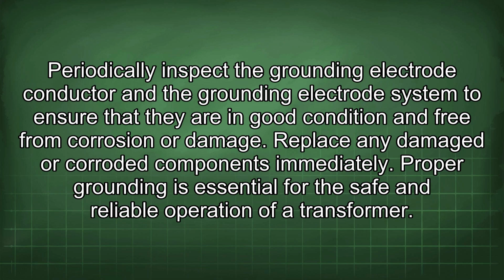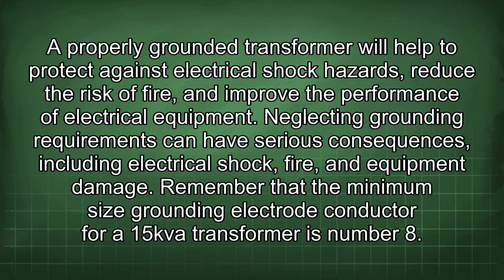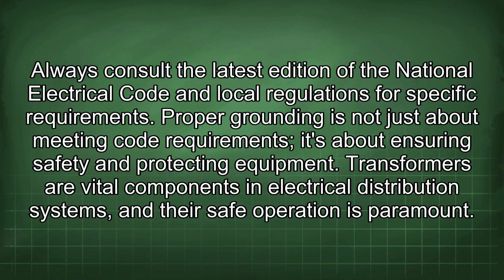Proper grounding is essential for the safe and reliable operation of a transformer. A properly grounded transformer will help to protect against electrical shock hazards, reduce the risk of fire, and improve the performance of electrical equipment. Neglecting grounding requirements can have serious consequences, including electrical shock, fire, and equipment damage. Remember that the minimum size grounding electrode conductor for a 15 kVA transformer is number 8. Always consult the latest edition of the National Electrical Code and local regulations for specific requirements.